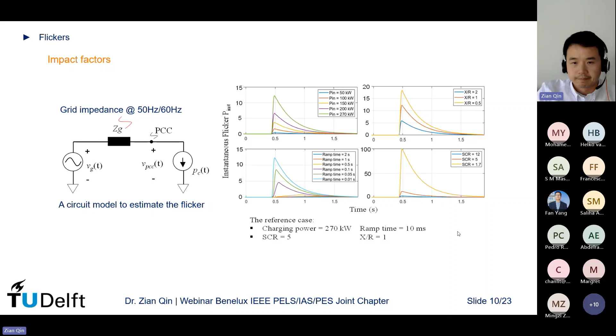So what would be the mitigation measures if you really have flicker issues there? Can you change the charging power? If the capacity of the grid allows you to go to higher power, usually you go for that, right? You cannot easily sacrifice charging power because of flicker issues. About the X/R ratio, that is a characteristic of the cable. That is something you cannot easily change. Short circuit ratio, again, is a parameter that you don't really have much freedom to change. But what you can do is the ramping up time of the charging power. If there are really flicker issues, then the easiest way is to slow down the ramping up of the charging.